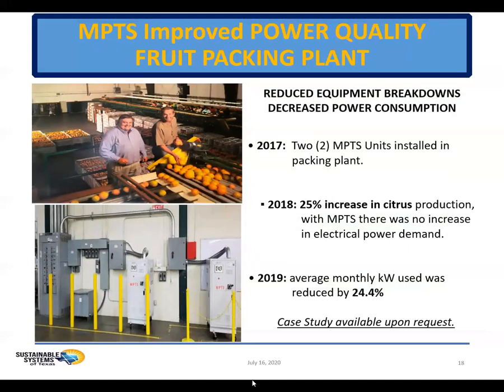In 2017, 2 MPTS units were installed in their fruit processing plant. The plant had been experiencing many power dips that were shutting down the plant. These unplanned shutdowns greatly affected the plant's output and the plant's ability to produce product on time and every time. During 2018, the local citrus production increased by 25%. They had a bumper crop. But with the two MPTS units installed, there was no increase in the plant's electrical power demand. In 2019, when the fruit production returned to normal, the monthly kW used was reduced by 24.4% over that previous year.